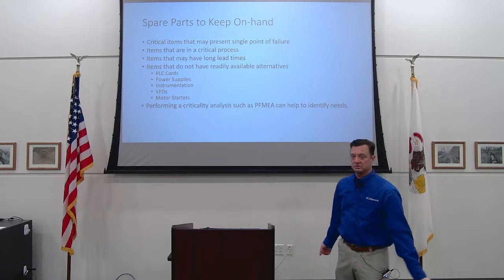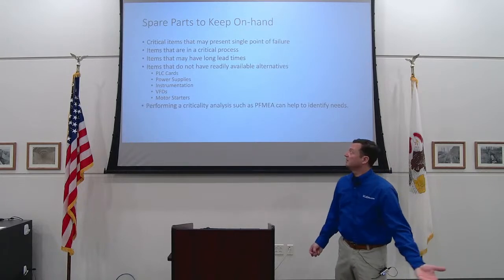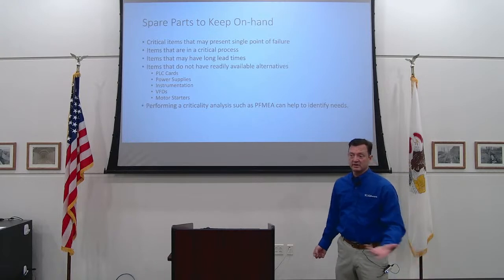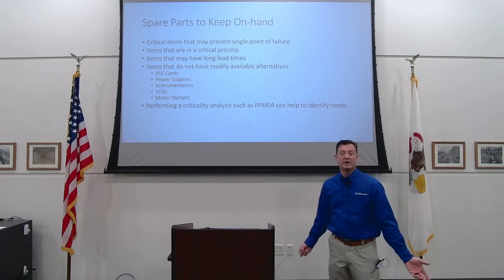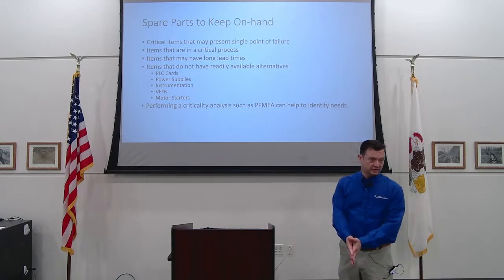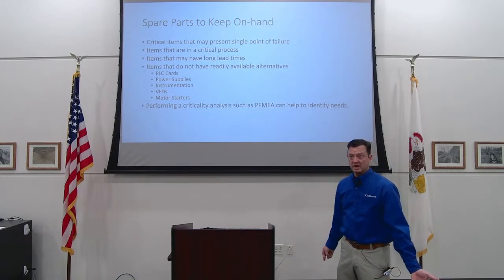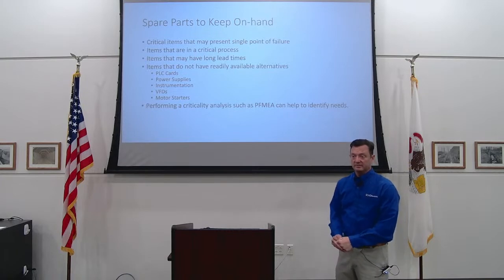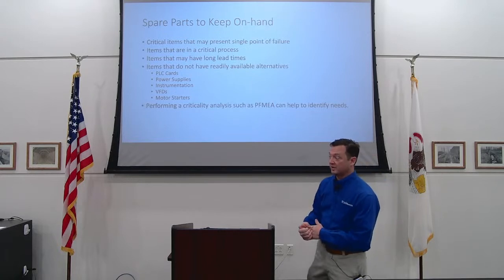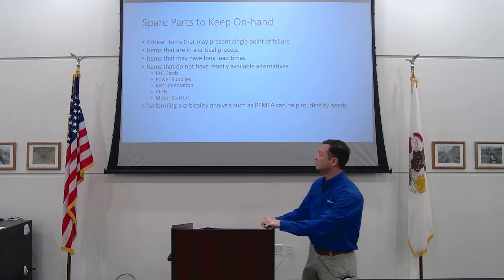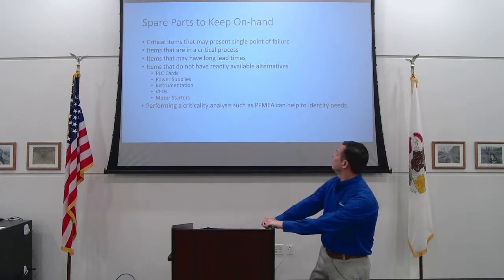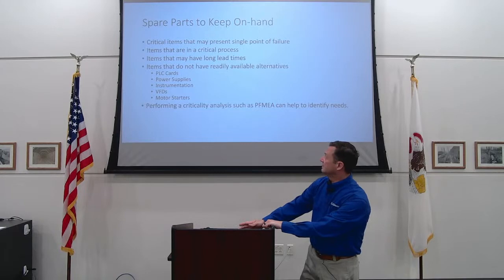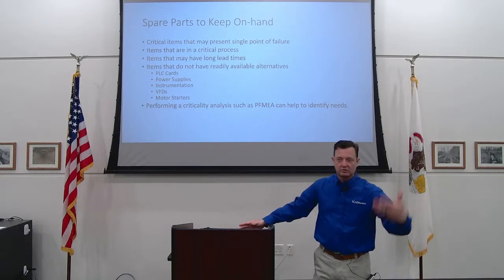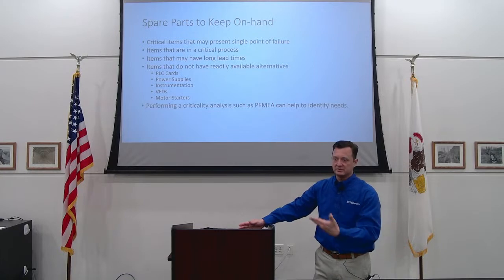Also look at items that aren't readily available. It wasn't an issue two years ago, but we're seeing regularly 14-month lead times on PLC processors and PLC cards. It's a different world - things just don't happen quickly, and you can't get parts. So that's something that really has to be taken into account. Then do some criticality analysis, rating your equipment and different processes to figure out where you really need good backups.